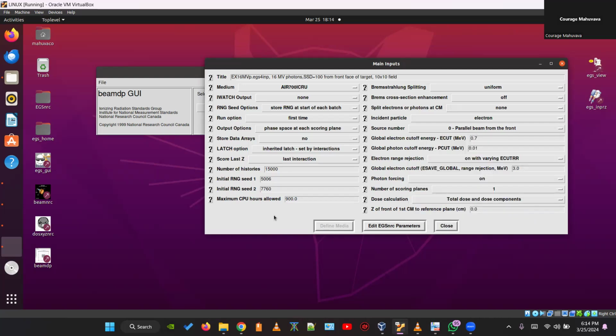You have different types of sources that you can use, but for a linear accelerator, it's simply a narrow electron beam that hits a target. So this is good enough for us. If you are, however, simulating something like an X-ray tube, either diagnostic or therapeutic. Remember, a linear accelerator has got a transmission target. In other words, the beam simply comes and passes through the target. A reflection target, on the other hand, that is used for diagnostic X-ray tubes, would require a beam that comes from the side, impinges onto the target, and then is reflected towards the patient.